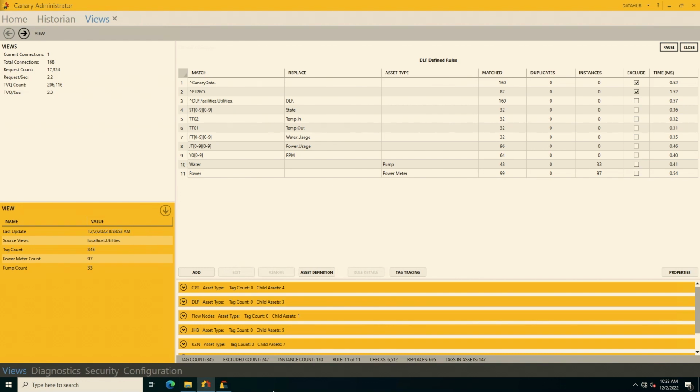have existing tags that come from one system with a different naming convention because they were configured some time ago, and then now you have some other tags that are now newer or they were built with a different standard and you want to make sense of all of them. So all these rules that you are seeing on the virtual view screen, they are built out of a regex language, right? So it's technically a string manipulation language that Tebe is creating rules with to take the tag naming structure of the different tags and kind of filtering through them, creating assets and just making it more human readable.